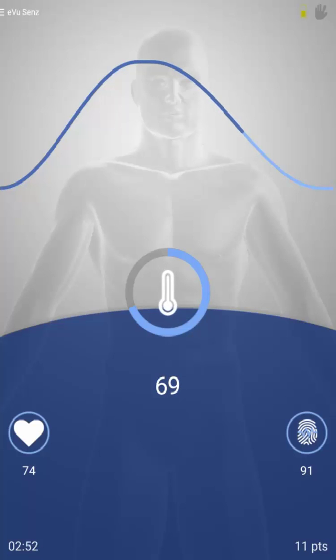The system has an integrated real-time artifact detection feature, such that the TPS sensor will realize when fake data is being introduced and signal to the user to stop the movement generating the fake signal. I'm going to start moving my hand that has the TPS sensor on it, and notice at the upper right, there's a red hand symbol that's appeared and starts shaking to signal that I'm moving too much for good data measurement. This is possible because the TPS sensor has a built-in accelerometer that detects movement.